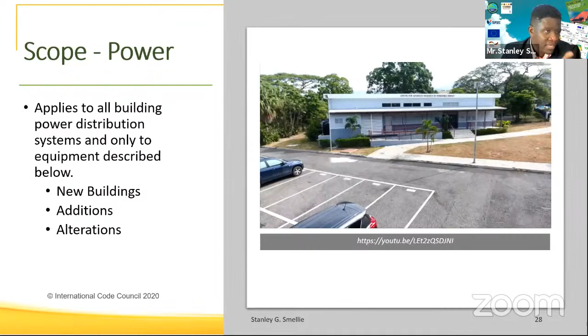For this net zero energy building, I'll give some specific examples. To meet ASHRAE 90.1 compliance for power, you want to ensure that the voltage drop in the different feeders supplying power to the building has a maximum of 5%. This demonstrates that all your conductors need to be sized appropriately, the type of wires utilized, the different loads per circuit, and the type of circuits are in conformance with established international best practices as well as your local electrical code. So everything has to be in conformance from an electrical standpoint.